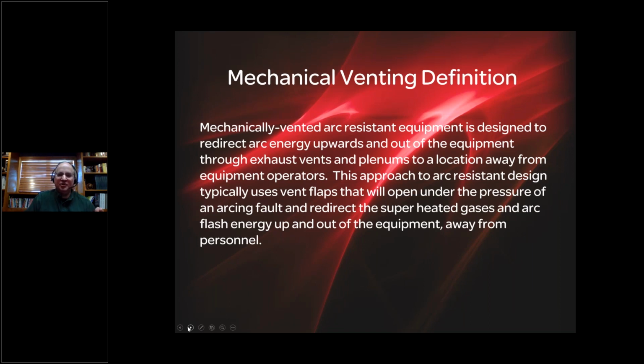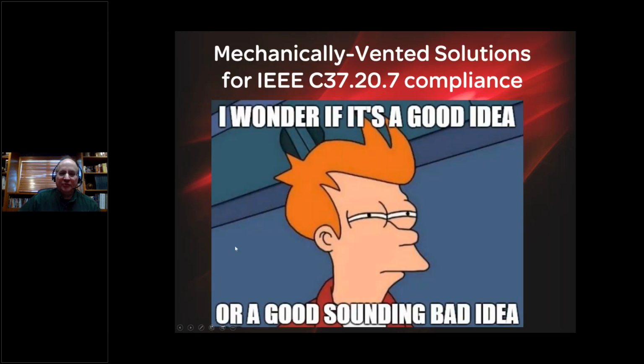So the mechanical venting, the very definition is we're going to take the energy exhausted out to a location away from equipment operators. And this approach to arc equipment design usually, not always, but usually uses vent flaps that open under the pressure of the fault and redirect the superheated gases away from any personnel. So again, the focus is on safety, but the equipment itself frequently gives its life in the performance of its duty. So if you're considering mechanically vented solutions to C37.20.7, ask yourself, because arc resistant sounds good, sounds better than non-arc resistant, knowing the dangers of arc flash events, if it's a good idea or just a good sounding bad idea.